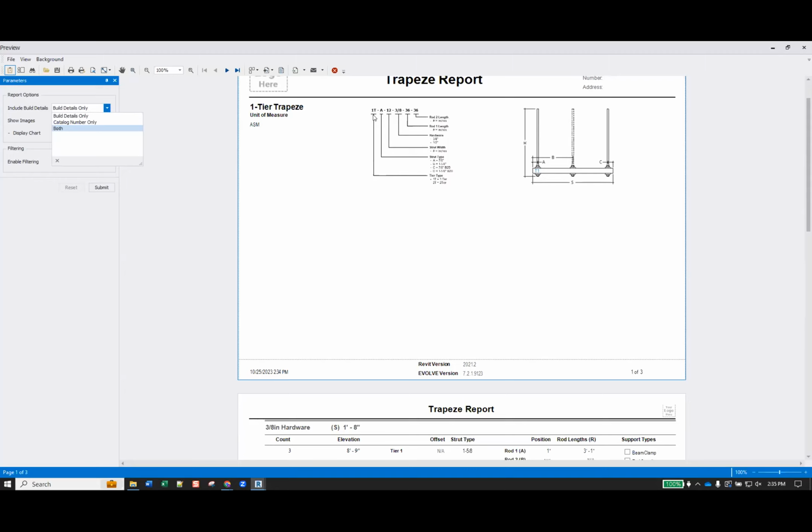We see this quite often when you're fabricating things like hangers, where there's variances in the fabrication method, but you don't need, say, a drawing to build it. You come up with a standard nomenclature. It's essentially a catalog number. You learn and train your people how to read the catalog number, and basically they can put together a trapeze hanger based on the value set here.